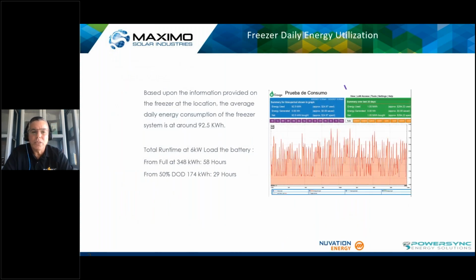As with any load, you need to understand precisely what the consumption is going to be. It was interesting because the equipment, the load to be served, wasn't built yet when we began the design, so we had to go back and do testing to update the design throughout the process. We used a regular 3-phase system to log the information and monitor it for a couple of weeks, which let us see the consumption and peaks of the system. Next slide.